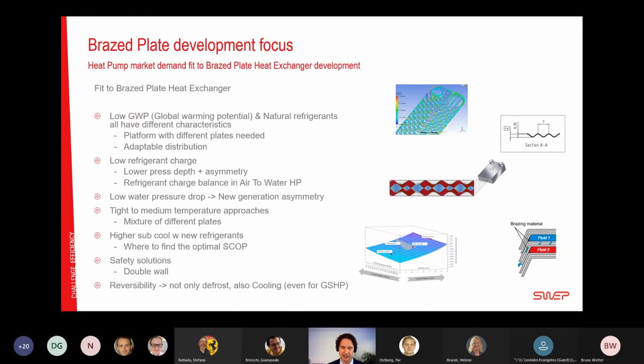From a safety solution perspective, we are developing our double wall technology. I will speak specifically on that in a slide later on. There are many different ways the heat pump manufacturers can use sniffers. You can have a venting system. But one way to do it is also to use the double wall. There are some downsides with loss of heat transfer efficiency, and also the cost, of course, when you have a double wall is a little bit higher than a single wall. But you do have a very safe solution where you will not mix the fluids.